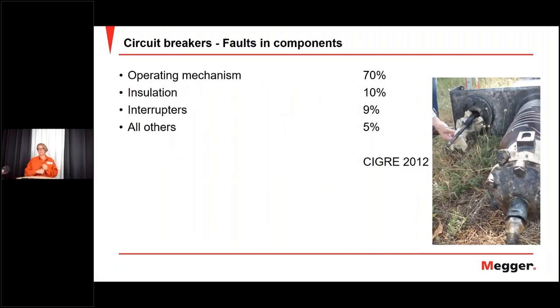And I want to mention, as I also mentioned on Tuesday, that it is important to realize that circuit breakers are not only the contacts. The manufacturers, of course, think that the gas and the arcing contacts and contacts are really important. And of course they are. But actually, when you look at numbers of faults, the operating mechanism is actually the main problem. Of course, it's also a matter of different severity of problem. But between 70 and 80% of the faults are actually in the mechanism, and as low as 9 or 10% are in the interrupters. So it's important to not only measure the contacts, it's important to have control over the whole circuit breaker.